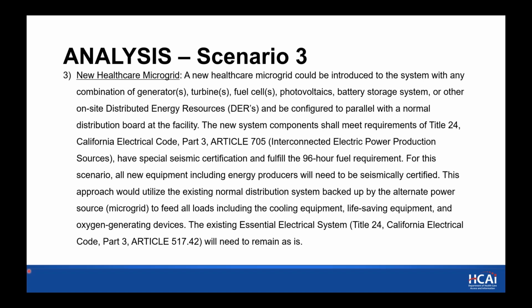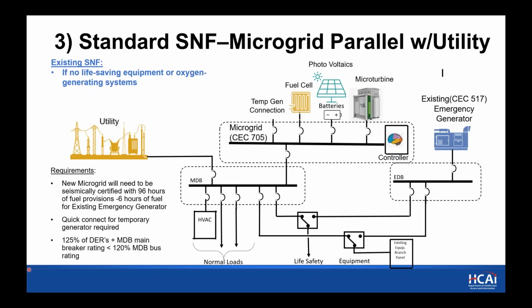Scenario 3 is a new healthcare microgrid, and I'll run through the slides with this. Now this gets a little crowded, but it starts off with the existing emergency generator on the right, the main distribution board on the left, and now in the center we're introducing a new microgrid. In this case, we don't expect that a microgrid is going to be designed and installed that has a microturbine and PVs and batteries and fuel cell, but we're just showing this for example. Any one of these could be used, any combination of these clean energy producers could be used, but essentially what we're pointing out is that there is a temporary generator connection required on this microgrid, and that microgrid then ties into the main distribution board and parallels with the main distribution board. So now in this case, you're backing up the entire facility with the microgrid.